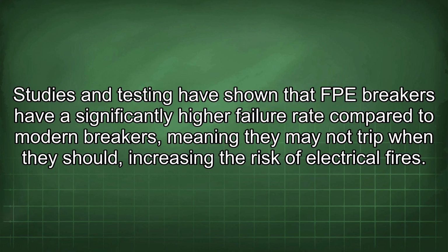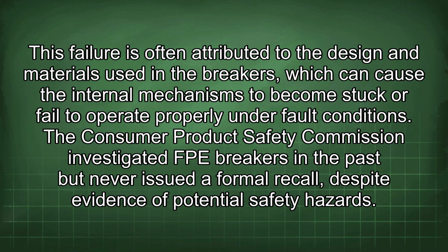Studies and testing have shown that FPE breakers have a significantly higher failure rate compared to modern breakers, meaning they may not trip when they should, increasing the risk of electrical fires. This failure is often attributed to the design and materials used in the breakers, which can cause the internal mechanisms to become stuck or fail to operate properly under fault conditions.